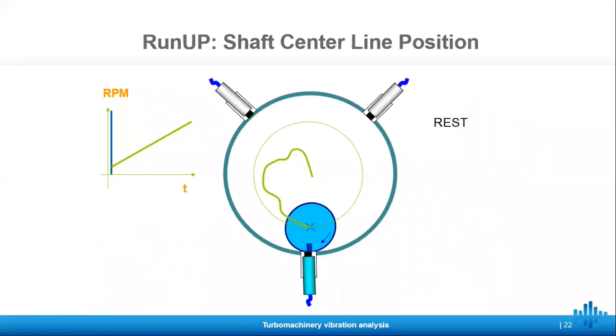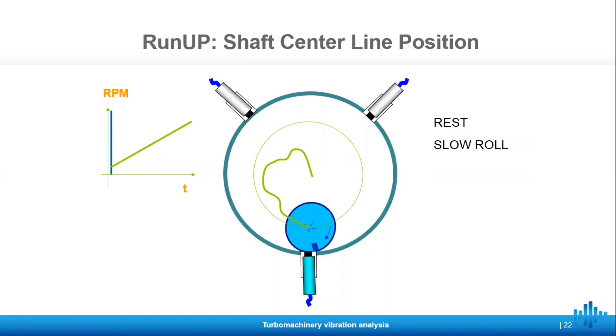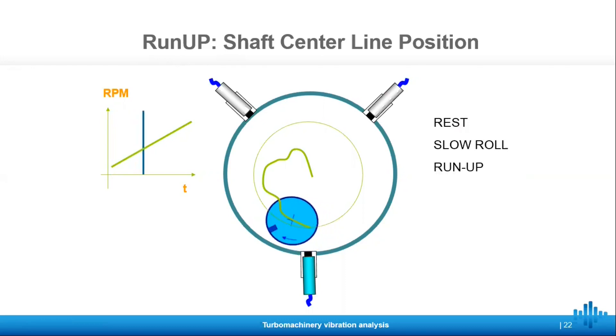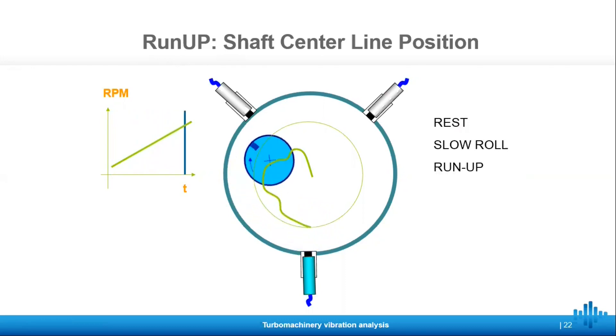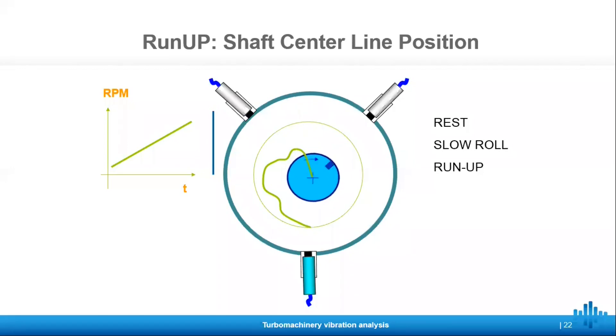Here we have one more animation to show how the shaft centerline position works. At rest, the shaft is sitting at the bottom of the bearing. As we begin the slow roll, it is still sitting at the bottom of the bearing while spinning. As the run-up begins, the shaft speeds up and moves about the bearing within the clearance circle until it settles at its operating position.